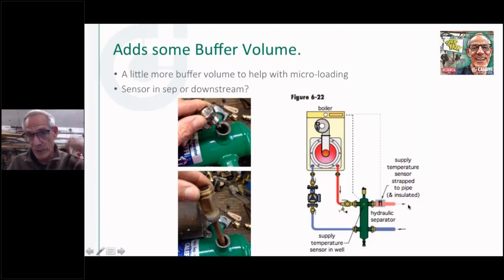When I put my circulator or multiple circulator pumps on this, I'm going to sense the temperature actually going out to my load, and then this boiler can accommodate that. It can modulate up and down based on what the sensor is telling it.